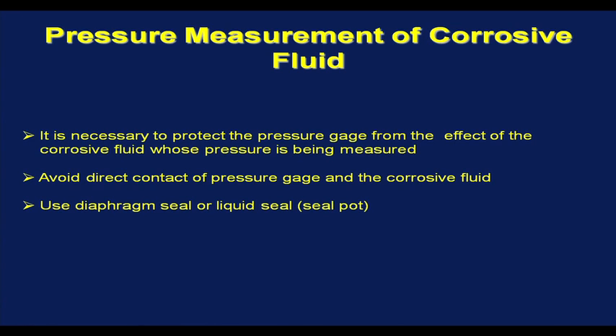Let us now briefly talk about how we measure pressure of corrosive fluid. When you want to measure the pressure of a corrosive fluid, it is necessary to protect the pressure gauge from the effect of the corrosive fluid whose pressure is being measured. So, you should avoid direct contact of pressure gauge and the corrosive fluid. We can make use of a diaphragm seal or liquid seal known as seal pot to avoid direct contact between the pressure gauge and the corrosive fluid. This can be done as follows.